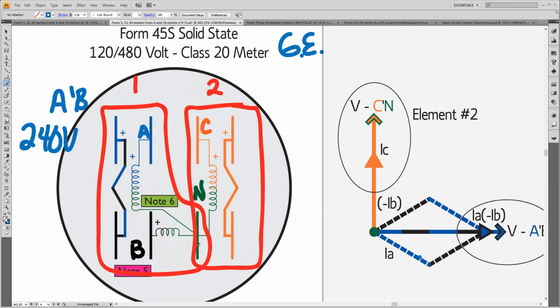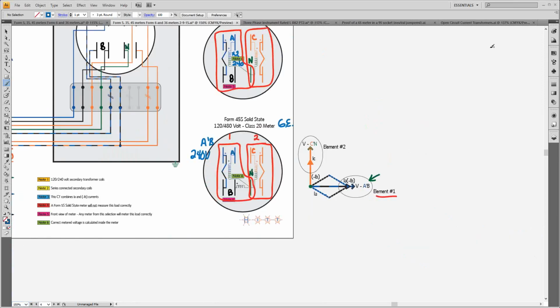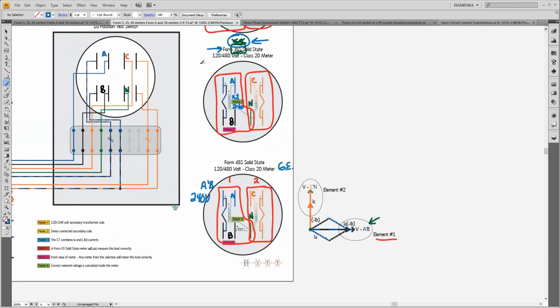I really don't have to rewire anything. I can pull out the 5S on the 4-wire delta, plug in this 45S, and these are the marked voltages. Let's zoom out a little bit and see if we can pick up the marked voltages from our socket. A phase voltage there, A phase voltage here, B phase and B phase, so that's the same, C phase voltage and neutral, and same thing here, A to neutral and C to neutral.